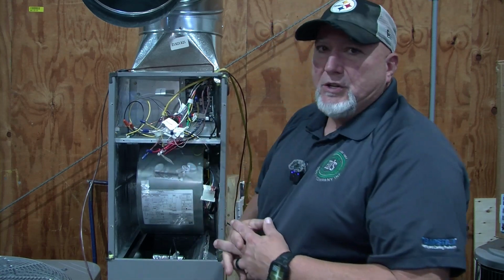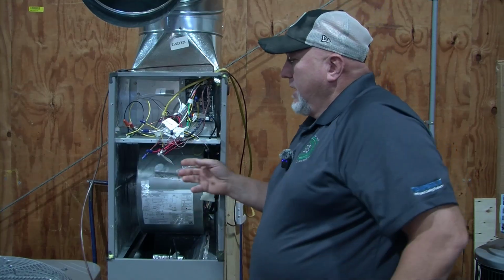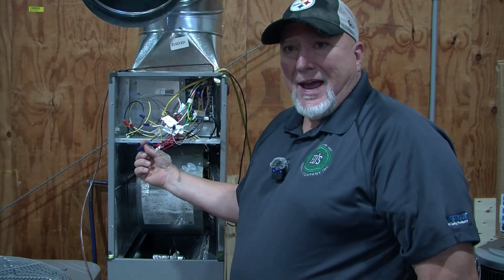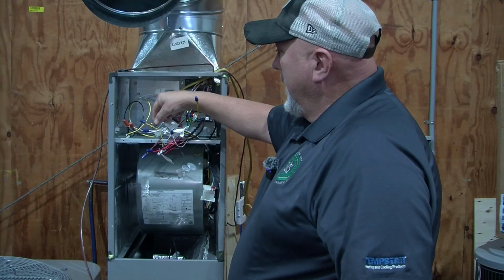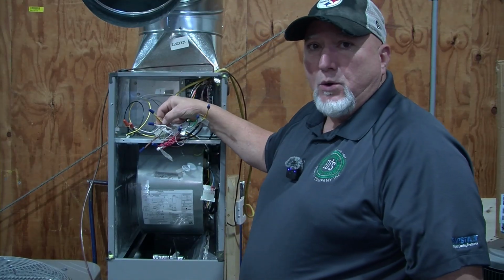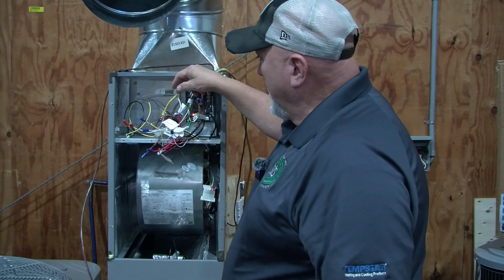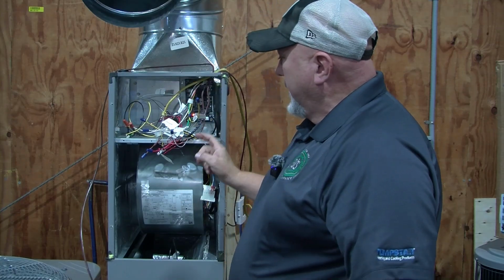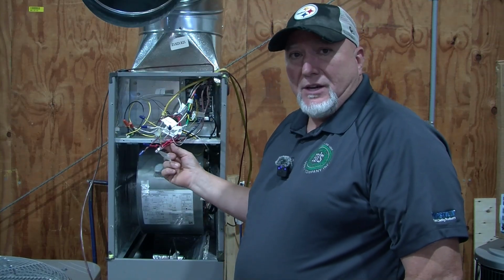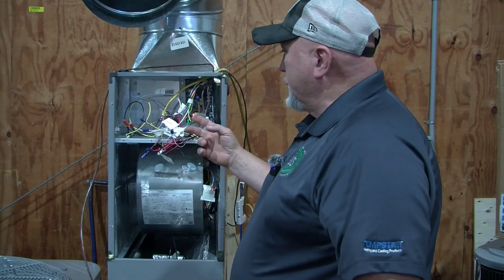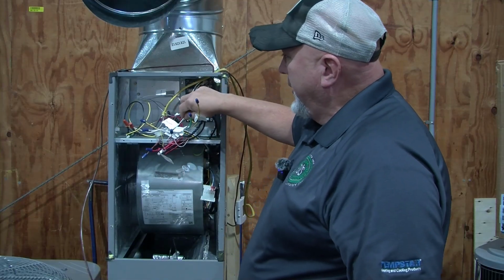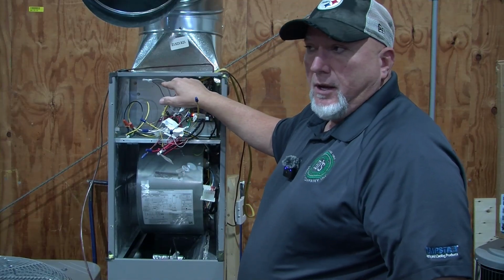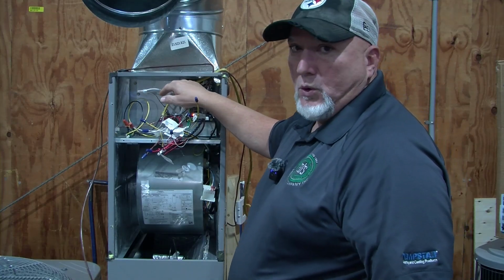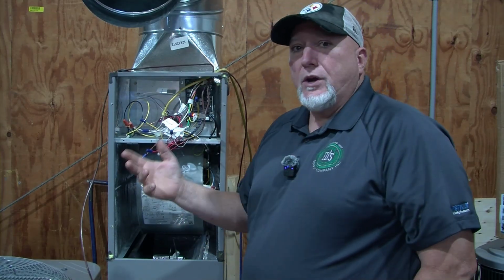So that's usually what we see in the field, is that either the common wire is not tied in, or this is tied in or broken with a float switch, or we see where the green wire is tapped into the condensing unit, or we'll see where they've cut this white wire here to tap in to the air handler or the heat strips or whichever way. But those are issues that I see.